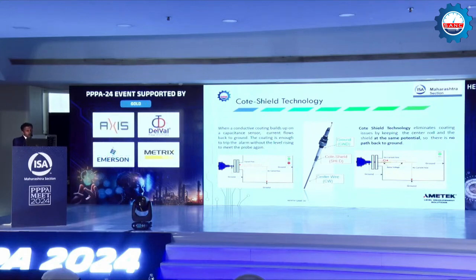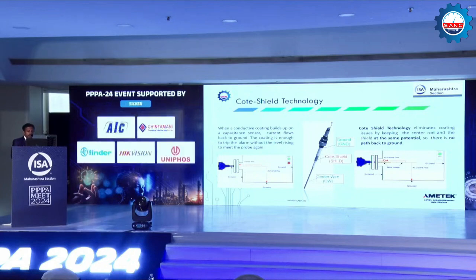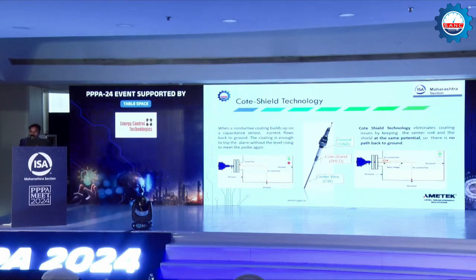In this picture, the first image shows the installation of a level switch without the Cote-Shield technology. In this case, the level rises and touches the probe, and then it comes down, but some liquid or sticky medium is left over on the probe, which creates a wrong signal, so you get a high level alarm even though there is no high level. What we did, as the center picture shows, is that there are three components in our sensor. It's a three-terminal probe: a ground, a Cote-Shield and a center wire.